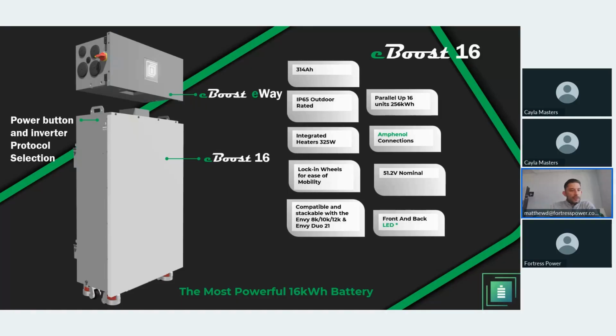Here, as you can see, this is the eBoost on the left side. It's comprised of two parts. You have the eBoost module, which is where the battery cells and the BMS are held. It is a 16 kilowatt hour battery, so 314 amp hour cells. And then you have the top part, which is the eBoost E-Way, which is short for electrical wire way, the same way that we do for the eForce. Now, like the eForce, it is an IP65 outdoor rated solution, perfect for outdoors and including climates with cold temperature, since it has integrated heaters that only consume 325 watts.